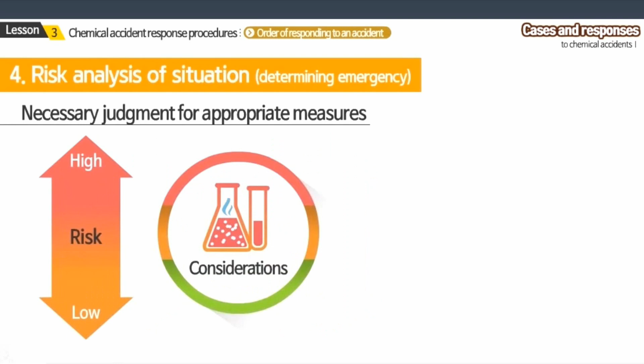Regarding harmfulness, the risk is high if the leaked chemical may affect human health, safety, or the environment, or if the chemical has not been identified or cannot be controlled due to valve failure, etc. The risk is high if the leaked amount involves mercury or hydrofluoric acid more than 40%, a combustible liquid, highly concentrated corrodible substance, or volatility of 2 liters or more, and 100 grams or more of highly reactive solid matter. The risk is high if the leaked place is publicly accessible, somewhere that does not deal with chemicals in normal routines, or is outside of the laboratory.